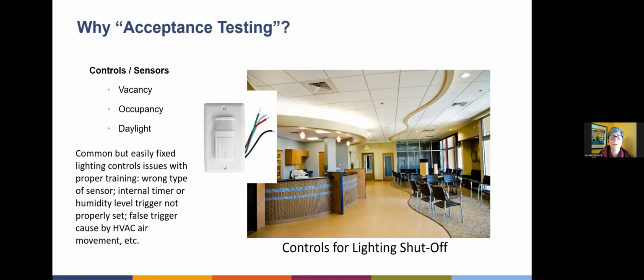It did go through a commissioning process, and mistakes happen - it was finally noticed by the occupants that the wrong type of lighting control was installed. A day lighting controller was put in a room with no windows, when it was supposed to be a vacancy controller, so when people left the room with no movement, things would shut off. There are also things that can be triggered by those vacancy sensors, like false triggers caused by the HVAC system turning on and causing movement in the room that keeps the lights on. Those kinds of things do happen.